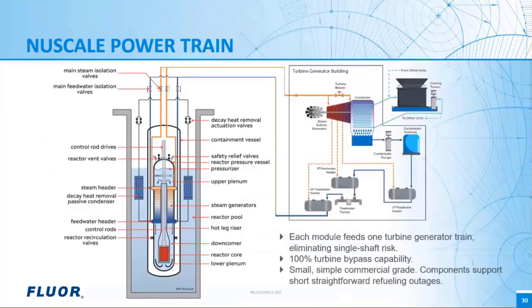Each of those NuScale modules sit in their own bay of a pool of water, and they feed their own dedicated powertrain. So if you have a 12 reactor plant, you will have 12 steam turbine generators. The advantage of this is that each turbine is smaller and can be purchased as a commercial off-the-shelf component, thus lower cost. And all the safety systems are in the reactor building in the NuScale plant.